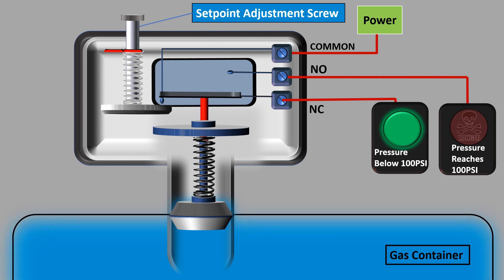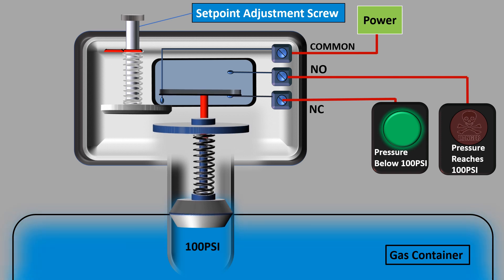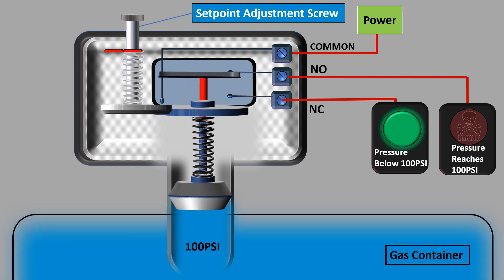We had already adjusted the tension of the range spring using set point adjustment screw so that it gets compressed when the inlet pressure reaches the set point. So when the inlet pressure reaches 100 psi, the piston is forced upwards by the inlet pressure compressing the range spring, and the piston will hit the trip button on the micro switch and change it over.